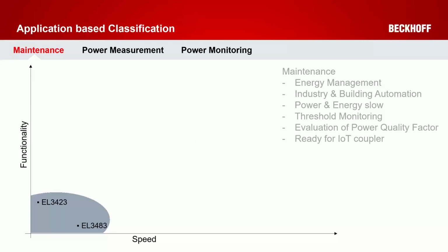We will start with the EL3423 and EL3483. They are designed for energy management in industry and for building automation. The focus of these terminals is the measurement of energy and monitoring of voltage, power, and frequency supported by thresholds. A power quality factor helps to estimate the local grid quality. The focus of these terminals is essential grid parameter delivery with slower update rates. So these terminals are good for economical applications and suitable for cloud-based analytics using our IoT couplers.